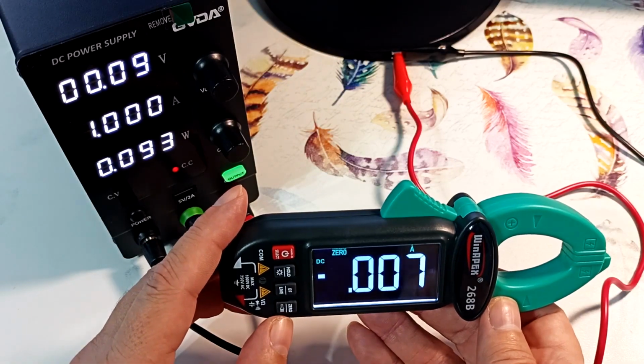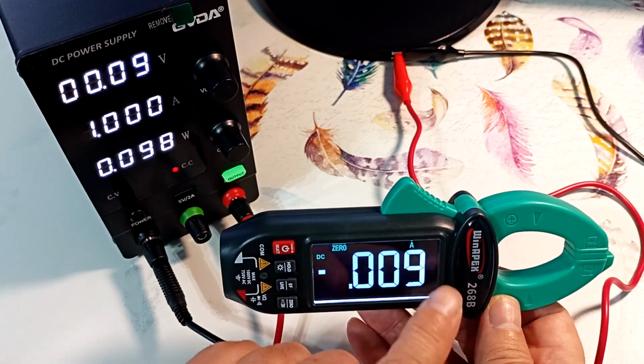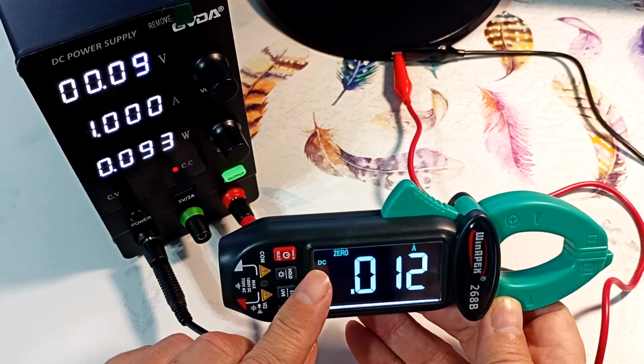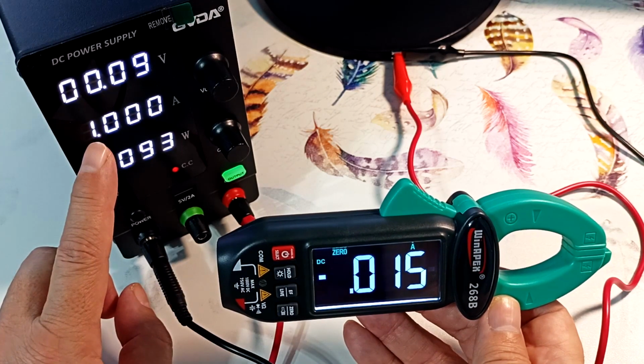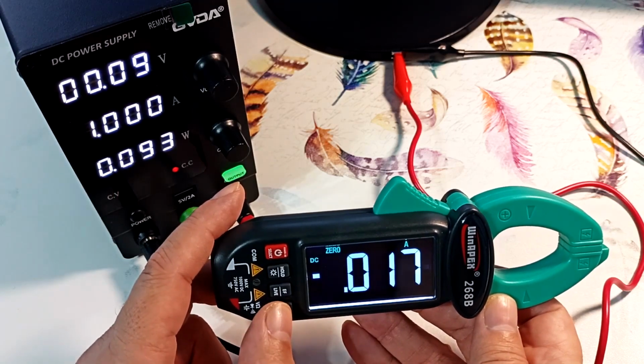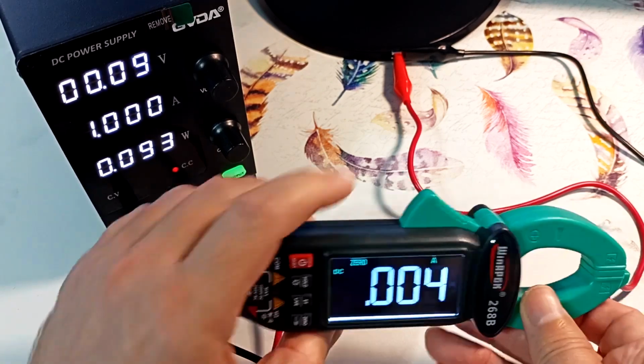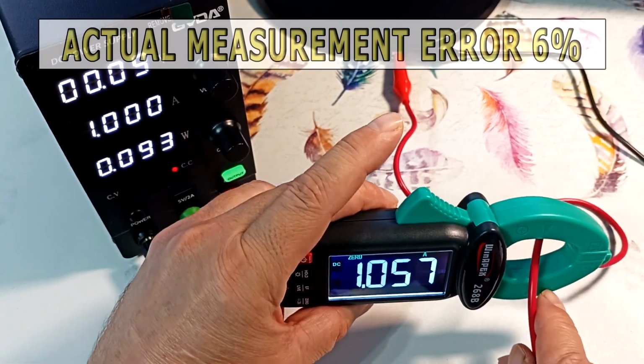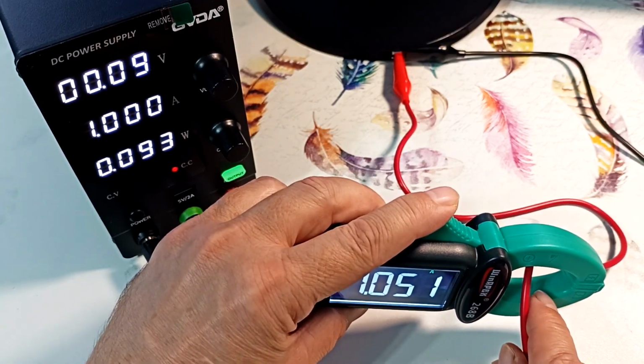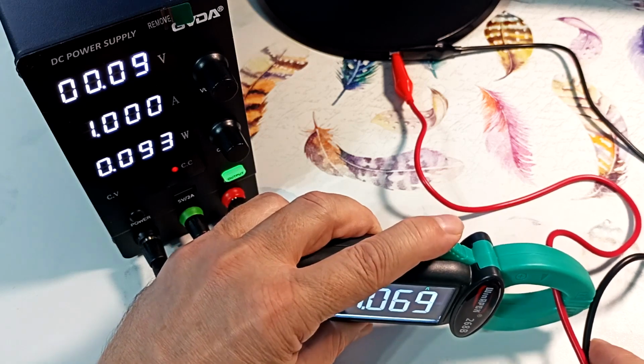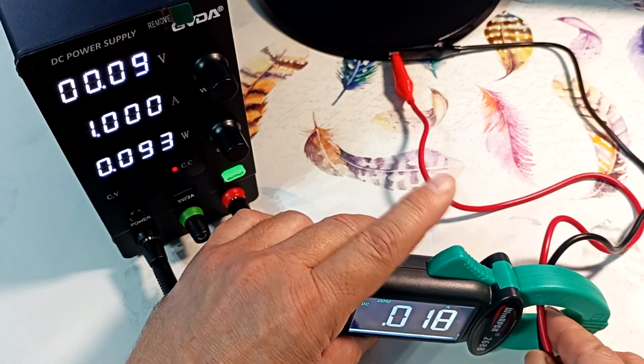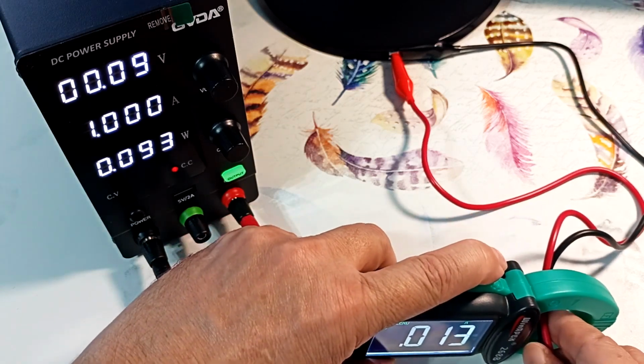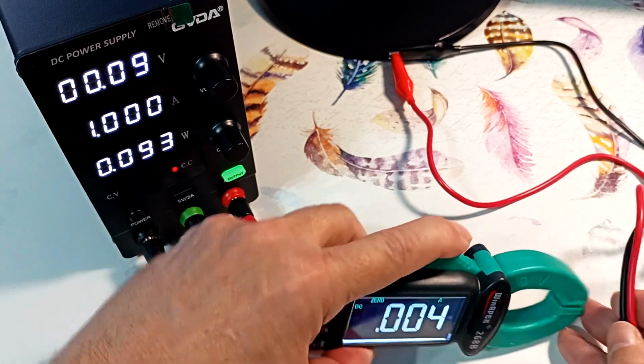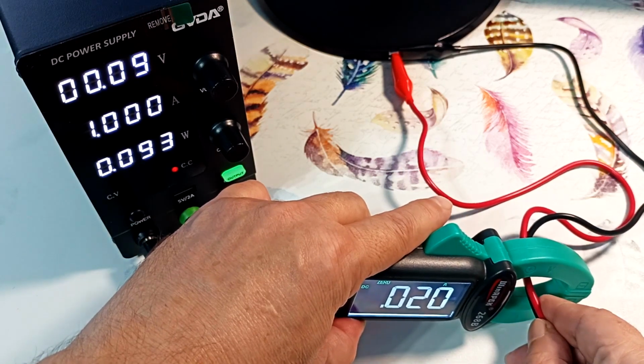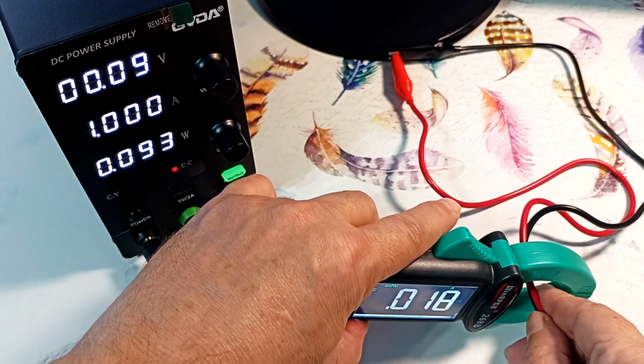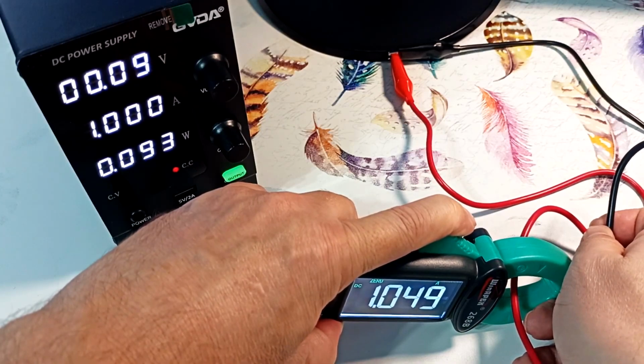So I set a more sensitive DC measurement range. We have 3 decimal places and a DC icon, which means direct current. The laboratory power supply is set to 1 amp. Before measurement, reset the readings to 0 using the 0 button. Let's measure it. Here we have 1.057 amperes. We can also measure the leakage current. To do this, we place the pliers on both wires at once. And we see that the current is near zero. Let's reset it to zero before measurements so that we can have a more accurate reading. And now we put it in. We got 20 milliamperes, although it should be about zero. If we measure one wire, we have a current in the region of 1 ampere.